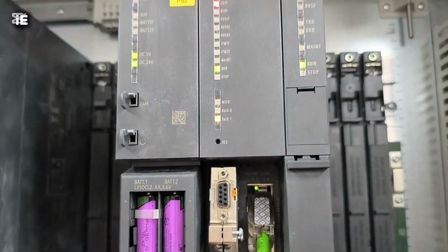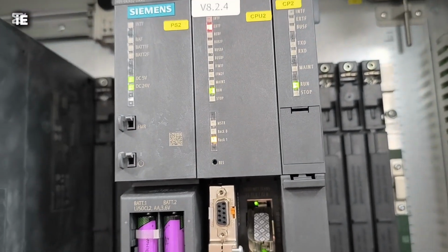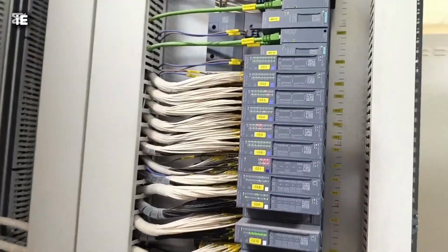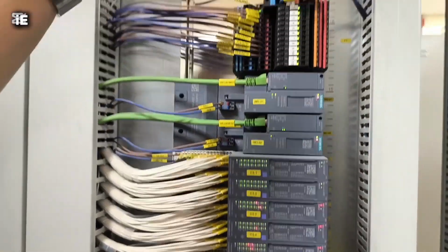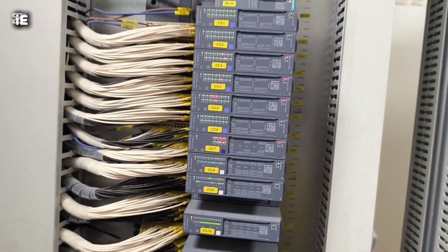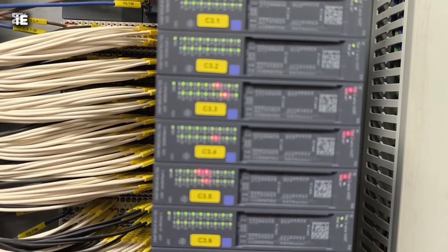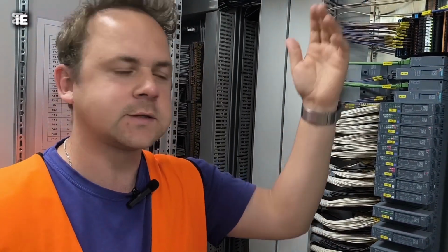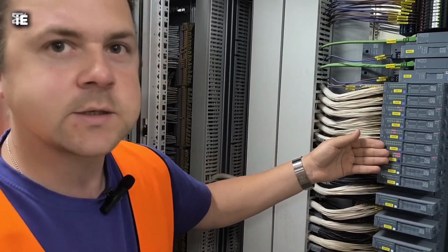So about the external fail LED, now it is showing fail. So we are using diagnostic for our 3 racks. Rack 1 and 2 is on the front part of these panels. Here we are on the rear part, and here we have rack number 3. So if all analog inputs, outputs will be connected correctly on the DCS part and in the process, then all these LEDs should be green.